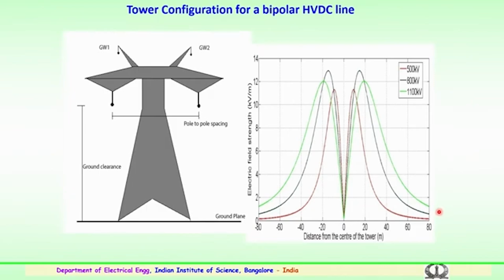This is a similar study conducted for the tower configuration for bipolar HVDC transmission lines for various voltage levels, 500 kV, 800 and 1100 kV lines. The data for the tower details have been obtained from the utility and also from the literature. This is again a schematic of the HVDC transmission tower. You can see the ground clearances where the conductors are connected. This is a bipolar DC line. GW1 and GW2 are the ground wire connections 1 and 2 for a tower. This is a ground plane, and the distance between the two conductors gives the pole to pole spacing, which as per the standards for 500, 800 and 1100 kV have been taken into consideration while estimating the electric fields.